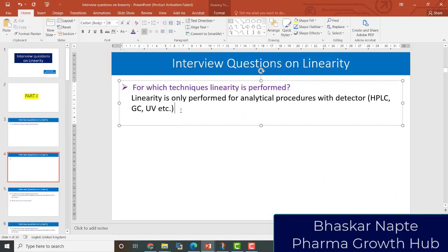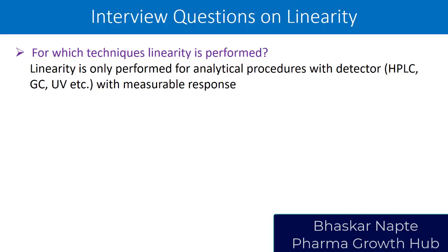So the answer is that linearity is only performed for analytical procedures with detectors — like HPLC, GC, UV, etc. — that give a measurable response. Even UV spectroscopy used for an identification test would not qualify, because in that procedure you are not measuring any quantifiable response. The detector is very important, and it must give a measurable response such as peak area or peak height, which can be compared against varied concentrations.